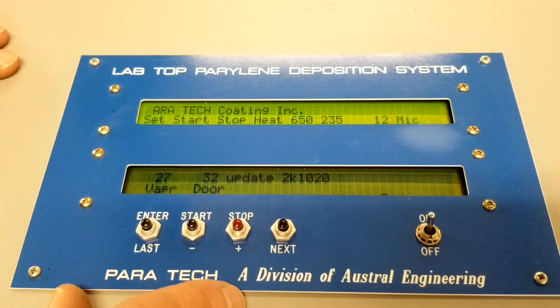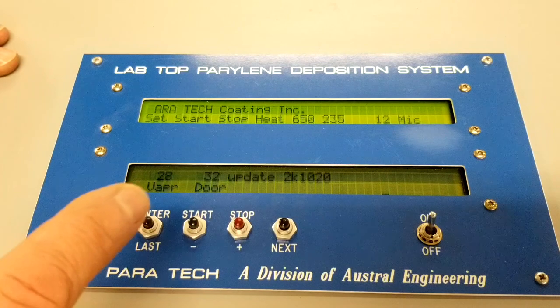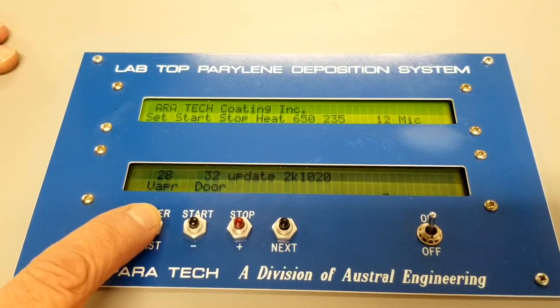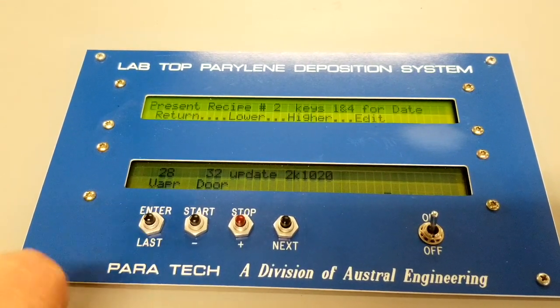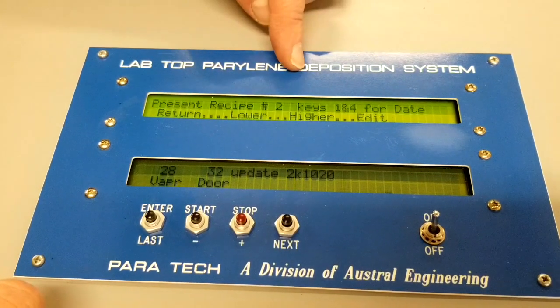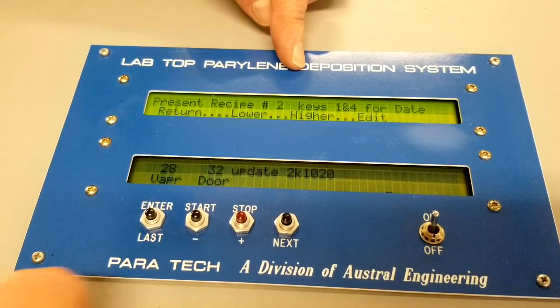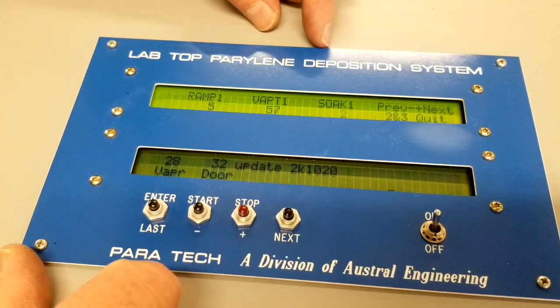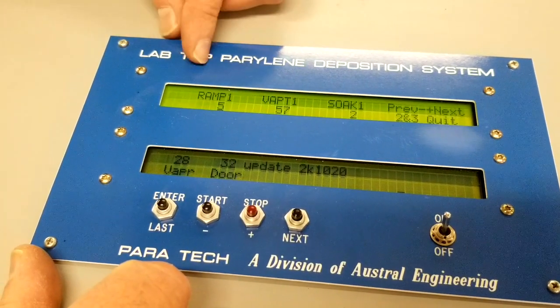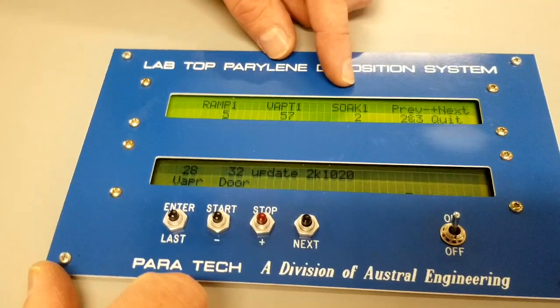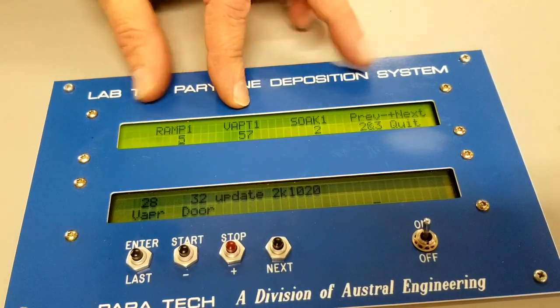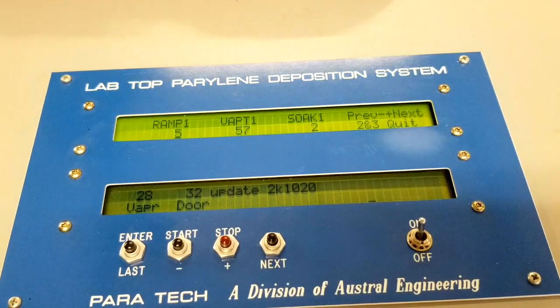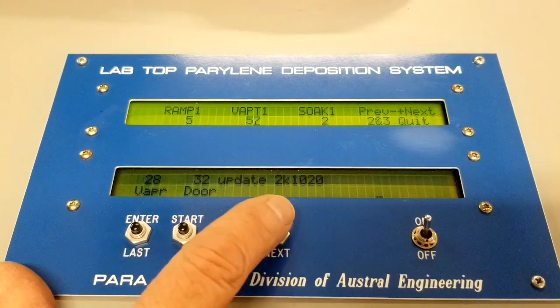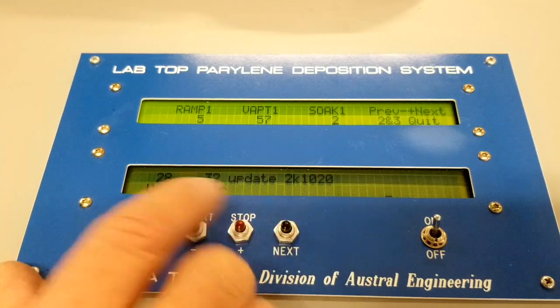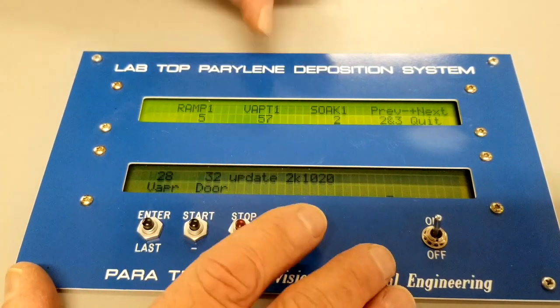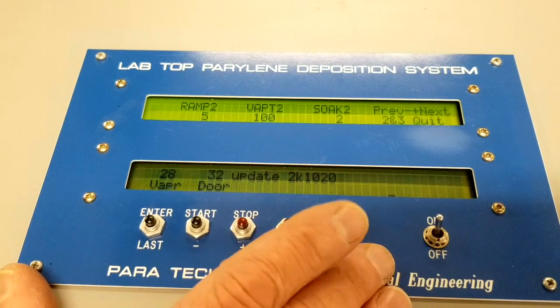And just to quickly go over this, first thing you would do is hit enter. Press and hold enter. This is explained in the manual that you'll receive. You do have a copy of that, and we're running recipe number 2 right now. And by hitting the next, we can edit that just to look at it. So I have a quick ramp soak. So this is 5 minutes. We're going to ramp to 57 degrees in the vaporizer, and a 2-minute soak. That's step 1. And it allows you to step through it. If you need to change it, you can use your plus or minus here. So as you can see, it's flashing under the soak 1 right now.